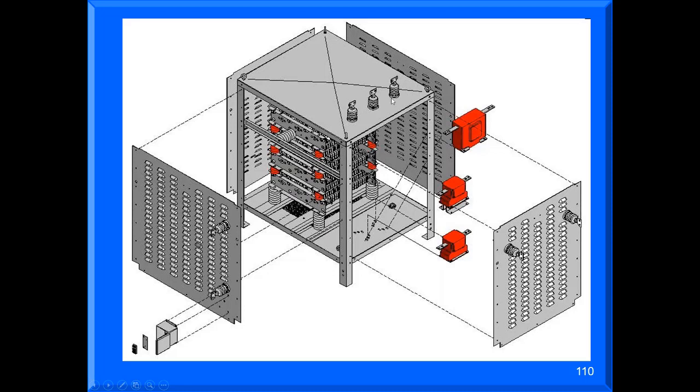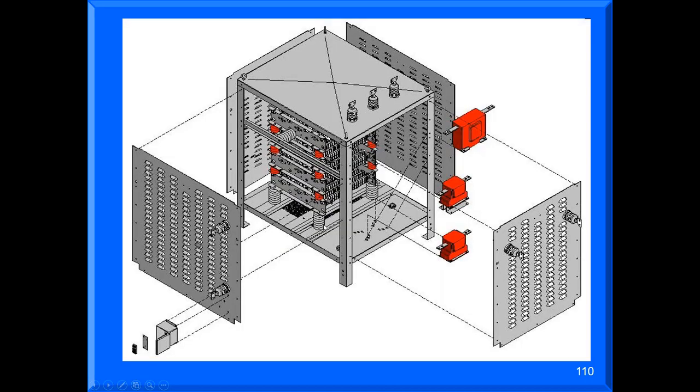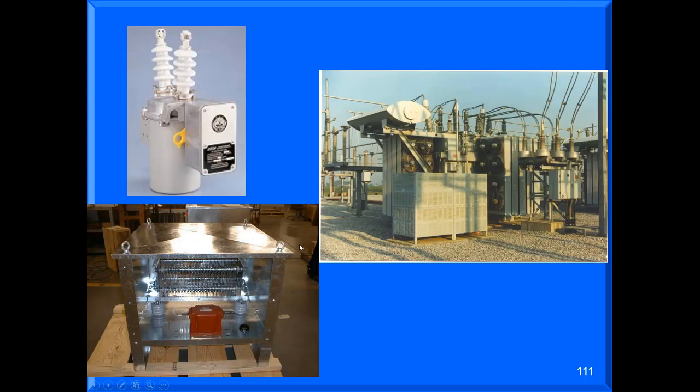If it's medium voltage, we can put bushings on there. I can put the bushing anywhere you tell me you want it: on the top, the side, front, middle, back. We also are going to have the CTs in there. I can give you a control box if you want to put a space heater in there, all kinds of stuff. Going back to the slide, I also do monitoring. We use a Statco. I can actually monitor the health of the resistor on medium voltage systems. Here's that contactor that'll open within 2 milliseconds.